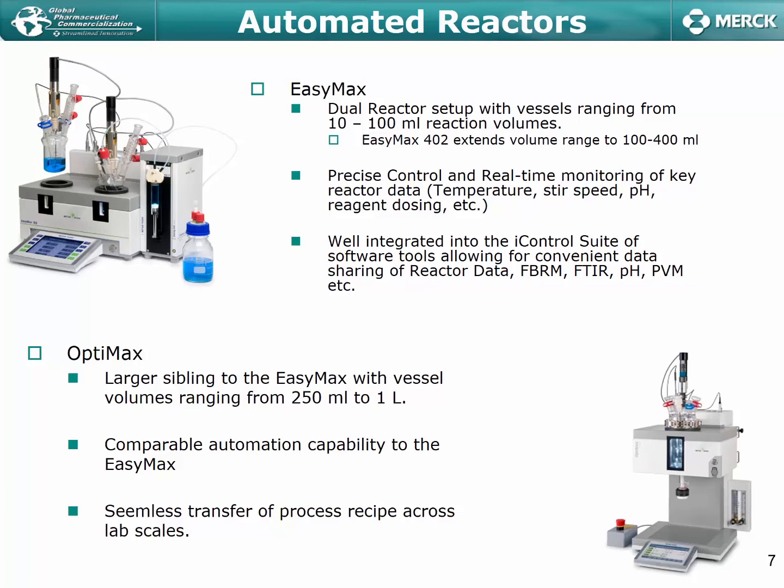The EasyMax is very well integrated into the iControl suite of software, which allows convenient data sharing across multiple platforms such as FBRM, FTIR, and PVM. It also has the capability to interface with Mettler's universal control box, which allows us to bring in analog signals from third-party vendors — enabling us to keep a robust dataset all self-contained within the iControl suite of software. In that regard, it's actually incredibly attractive.